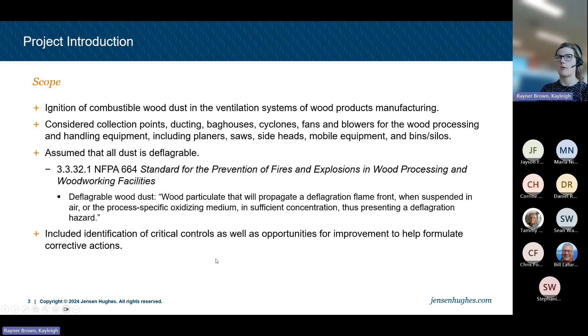We did assume that all dust is deflagrable. Per the NFPA 664 definition, deflagrable wood dust is defined as wood particulate that will propagate a deflagration flame front when suspended in air or a process-specific oxidizing medium in adequate concentration, therefore presenting a deflagration hazard. The work also included identification of critical controls, as well as opportunities for improvement, in order for operations to help develop corrective action plans.